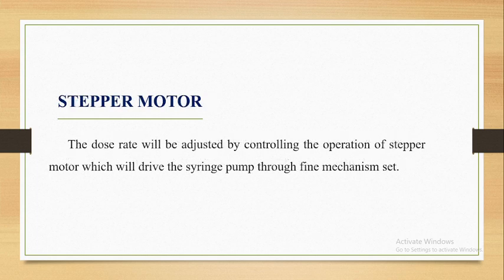Okay, next, stepper motor. The dose rate and volume will be adjusted by controlling the operation of the stepper motor, which will drive the syringe pump through a fine mechanism set.